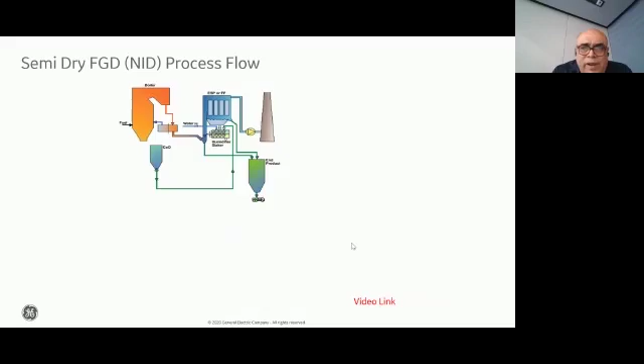It can be placed behind an ESP. In this picture, you don't see an ESP after the air preheater, because the semi-dry system can actually be set up for particulate control as well as SOx control. But in India, we have the requirement of fly ash collection and reutilization of fly ash, so definitely in India we are proposing this solution after the ESP. Even if you have an old plant with an ESP emitting higher particulate than what is needed under the environmental regulation, you can set up a semi-dry FGD system behind the ESP to meet the low emissions of SO2 as well as particulate.